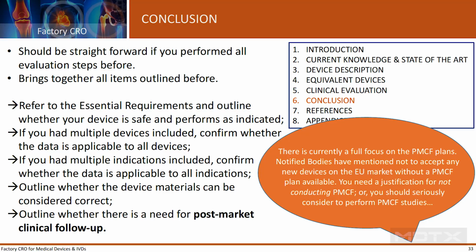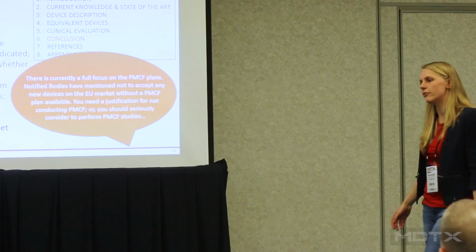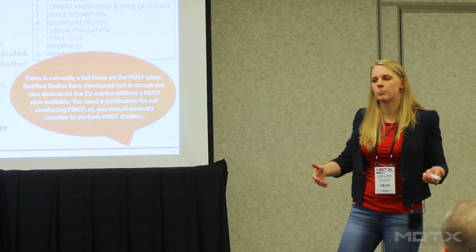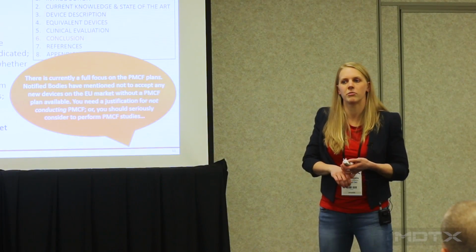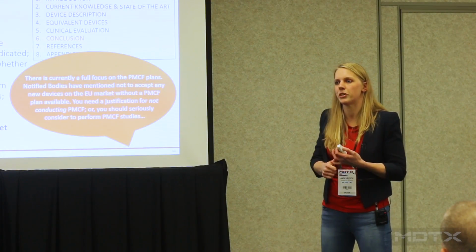But again, if you don't do it, have a good justification. It's getting very hard to have your product on the market without these post-market studies. But do know that the post-market clinical follow-up study doesn't have to be a randomized controlled trial costing you thousands of euros. It can be a very simple study as well. It depends a bit on the risk of your device and the outcomes of your evaluation.